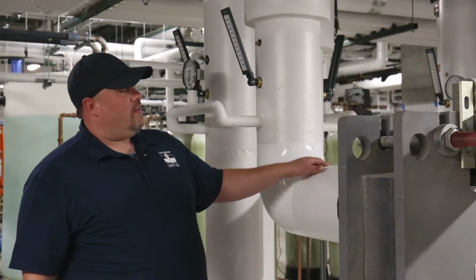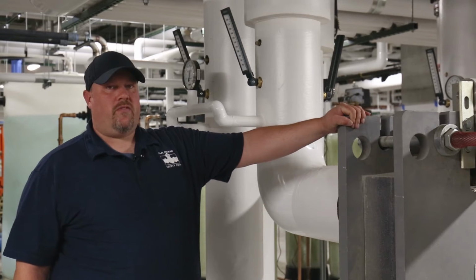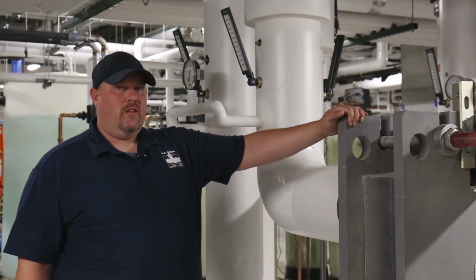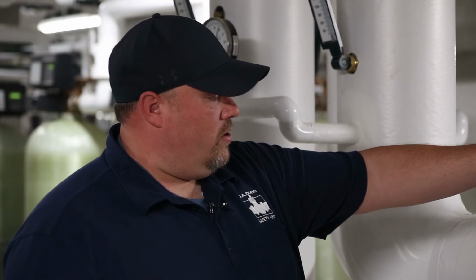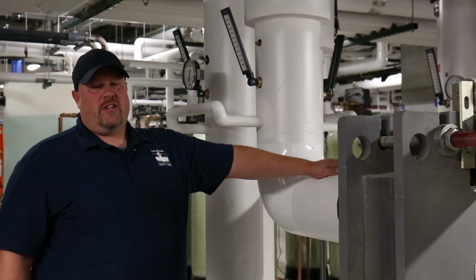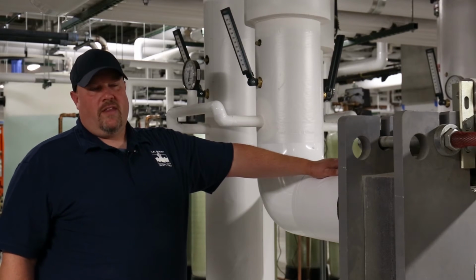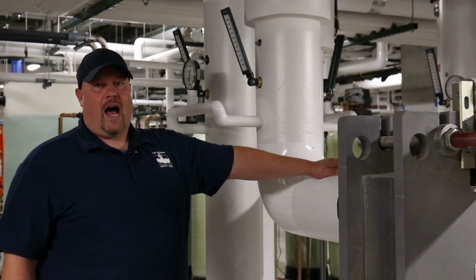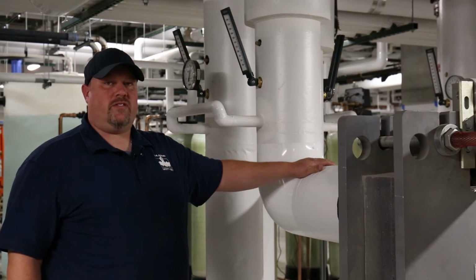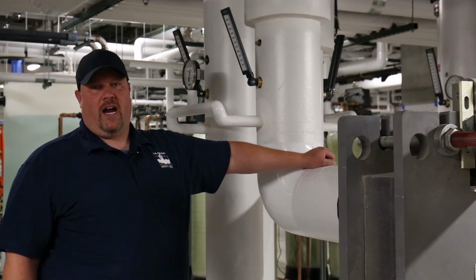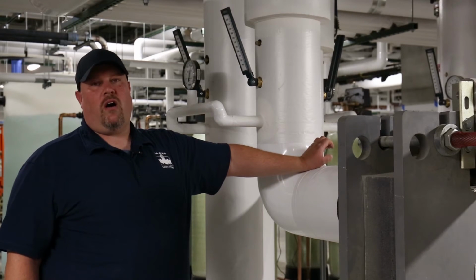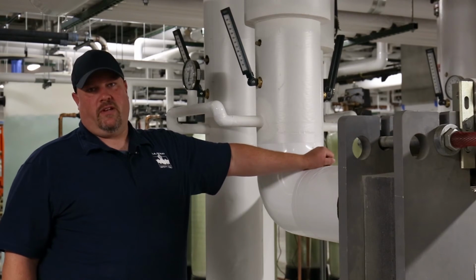Here we have our heating hot water heat exchangers that are tied into the glycol loop for the Convectipack system. These are either to reject the heat out to the system as needed or to recover the heat from the building as required per the control system. Here we have our heat rejection heat exchangers. They are for rejecting the heat from the chiller out into the system, being the glycol system, either to our air handler coils, preheats, or to our exhaust fan coil or exhaust units.